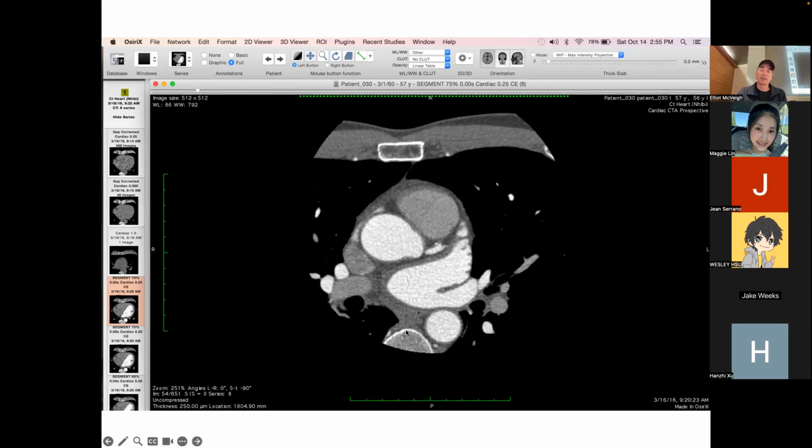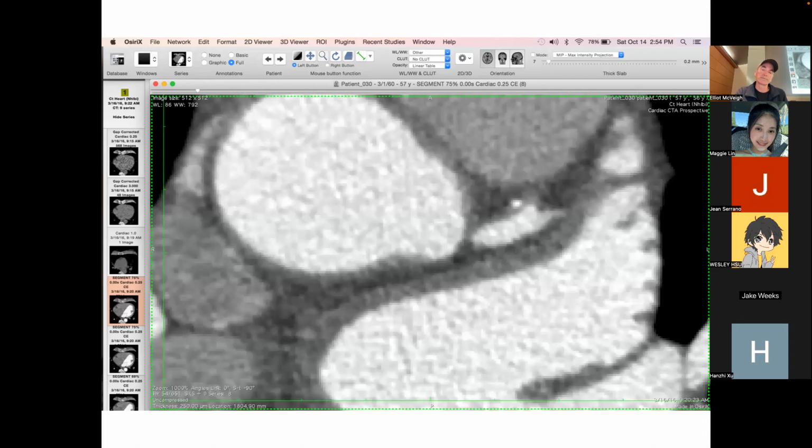And it looks pretty continuous when you look at it this way, because the individual values are very close together in space, right? And that's what we're displaying here. As we zoom in, you can start to see a few details which are interesting. One is you kind of appreciate the random noise in a uniform background. So this is blood in the left atrium. This is blood in the ascending aorta. And that blood should all have the same Hounsfield unit, should be the same number. It obviously isn't the same number because of noise processes. And so we have this variability here.